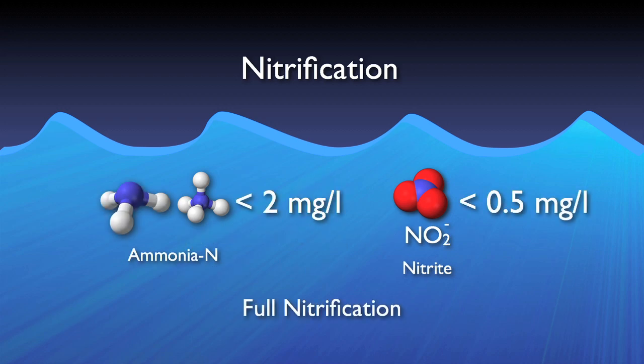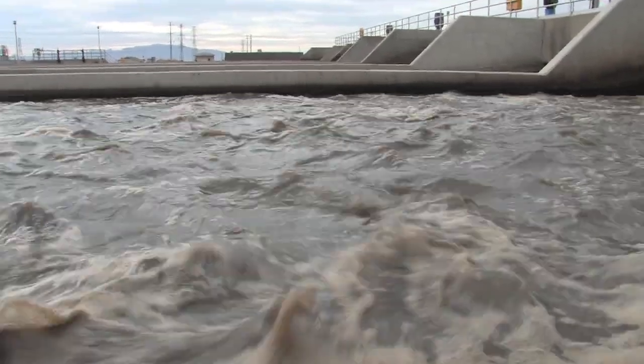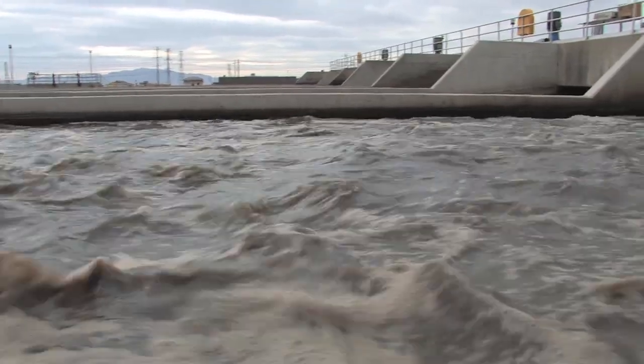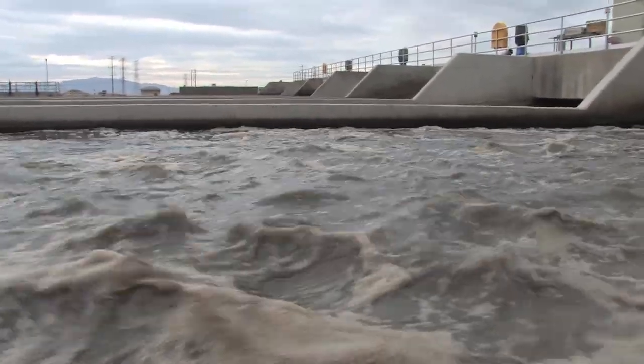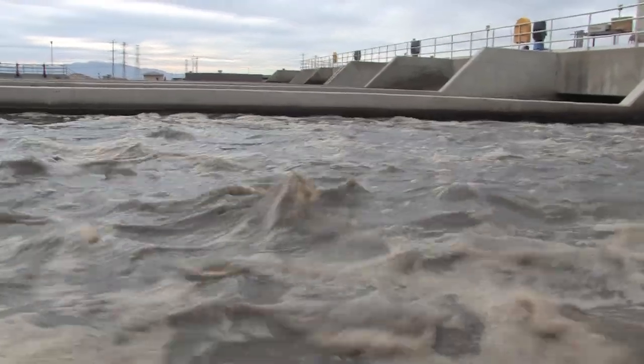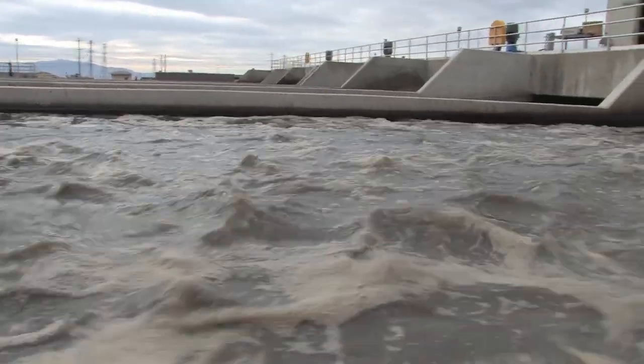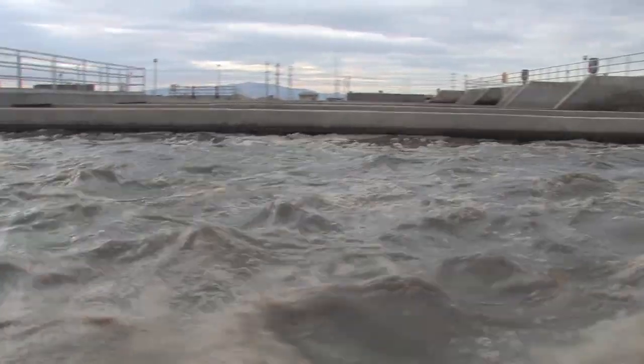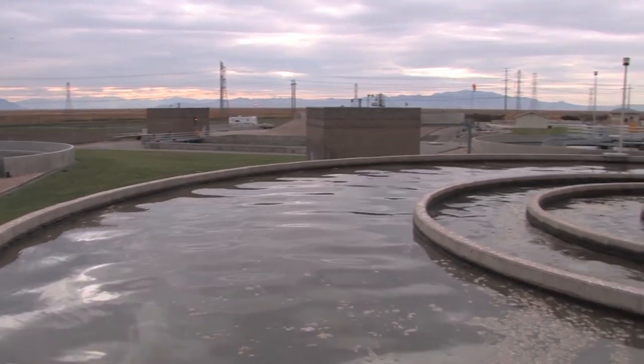Typically, full nitrification is observed when ammonia concentrations are reduced to less than 2 milligrams per liter and nitrite concentrations to less than half a milligram per liter. Nitrification is a very oxygen-hungry process. As a comparison, to remove 1 pound of BOD, 1.2 pounds of oxygen are required. However, to reduce 1 pound of ammonia to nitrate, 4.6 pounds of oxygen are required.